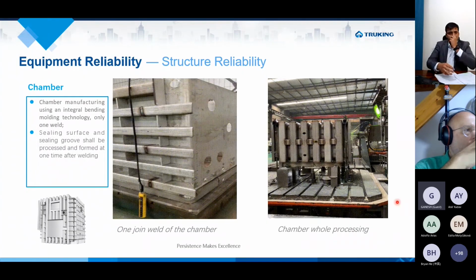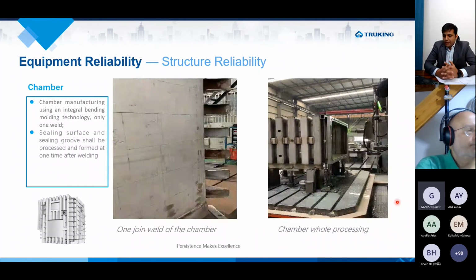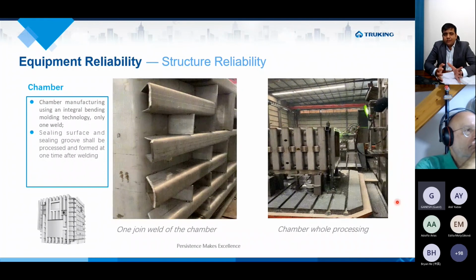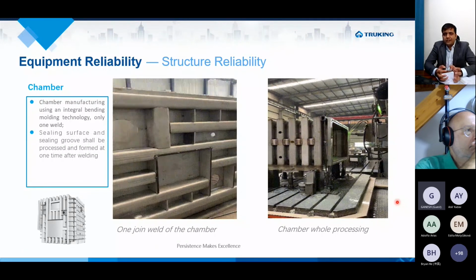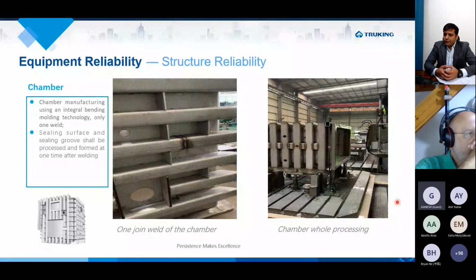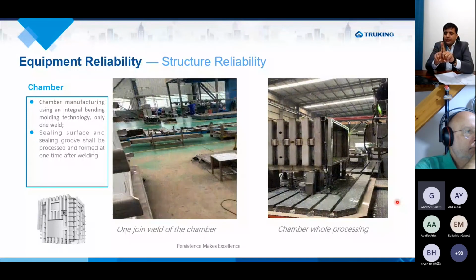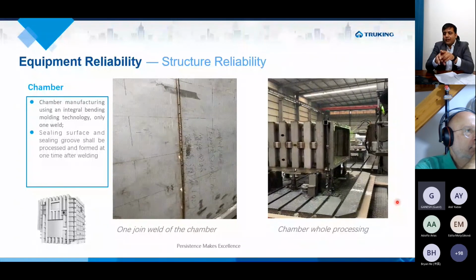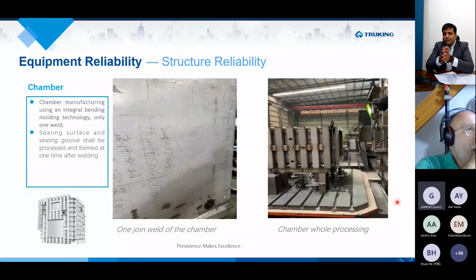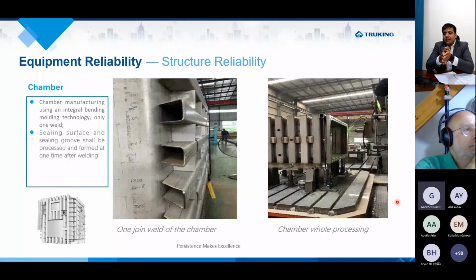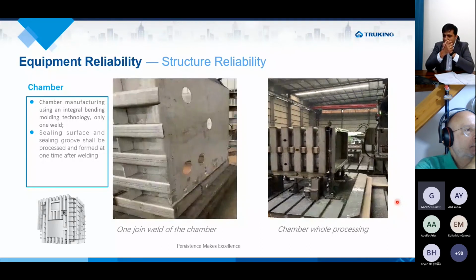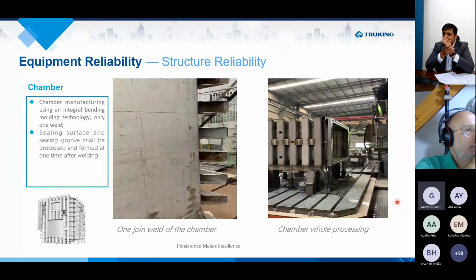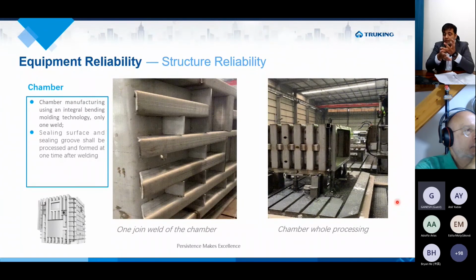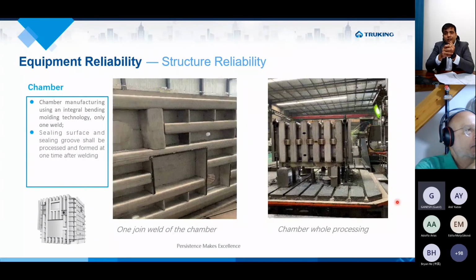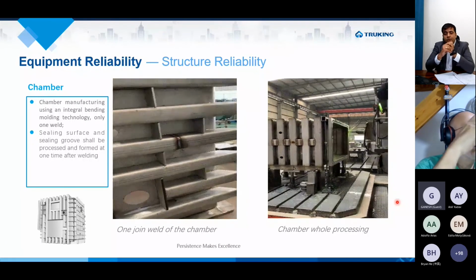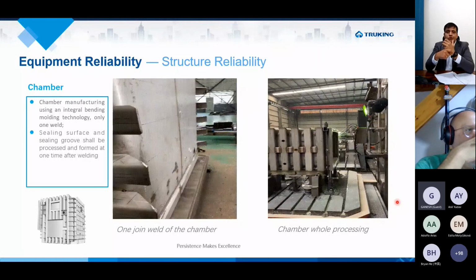Okay. The second major part of the machine is the chamber. Once the chamber of the lyophilizer freeze dryer is fabricated, it must not have any type of leakage or welding leakage. So at Truking, being in-house manufacturing, there is only one point to weld for the whole chamber, which is made in one piece, and that gives us better performance in terms of leakage. Sealing surfaces and the sealing groove are also processed and formed at one time after the welding process. This kind of fully automatic processing technique can largely reduce the risk of product failure while you process very expensive ADC drugs or any other cytotoxic product in the freeze dryer. The machine has to be capable for that particular point.